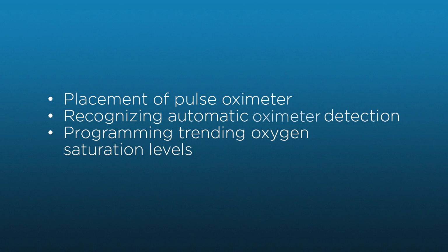In this video, you will learn how to use the oxygen saturation feature on Victoria. By the end of the video, you should be able to place the pulse oximeter on Victoria, monitor the automatic recognition of oximeter sensors, and program changes to the oxygen saturation.